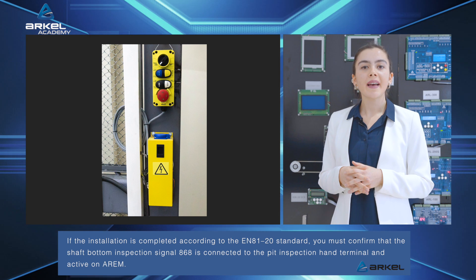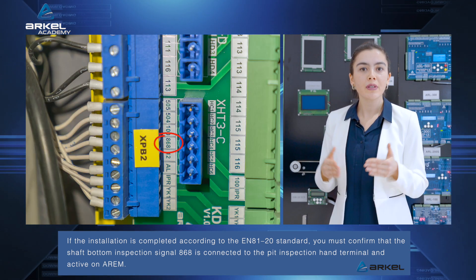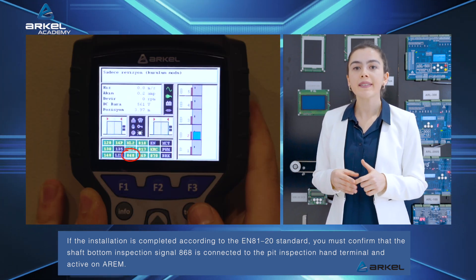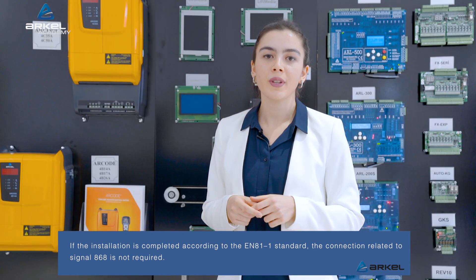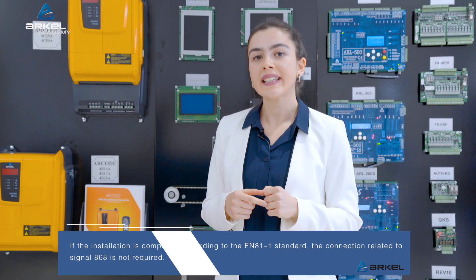If the installation is completed according to the EN81-20 standard, you must confirm that the shaft bottom inspection signal 868 is connected to the pit inspection hand terminal and active on AREM. If the installation is completed according to the EN81-1 standard, the connection related to signal 868 is not required.